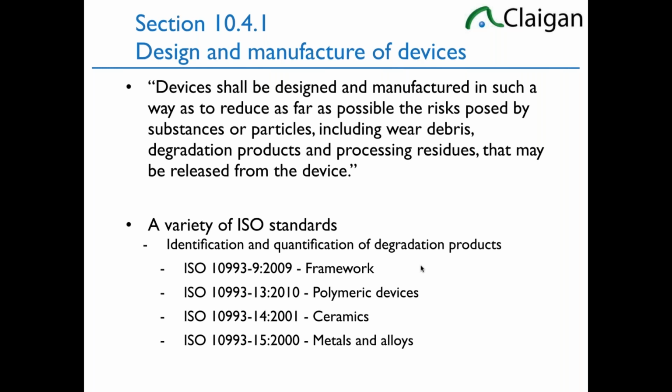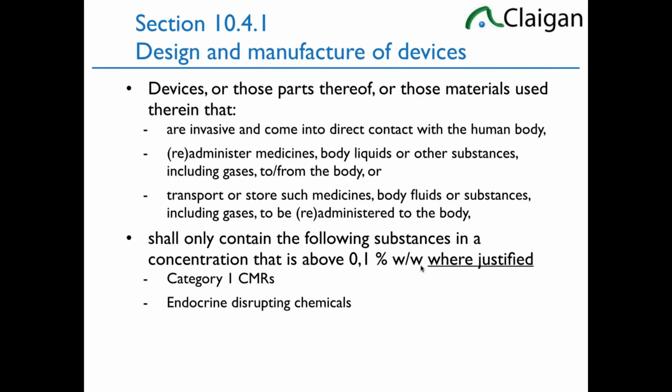Now this section has another piece to it. 10.4.1 has got this section and this section. And this is around devices or those parts thereof or those materials used therein that are invasive and come in direct contact with the human body, administer or re-administer medicines, body liquids, or other substances, including gases to or from the body, or transport or store such medicines, body fluids, or substances, including gases, to be administered or re-administered to the body.